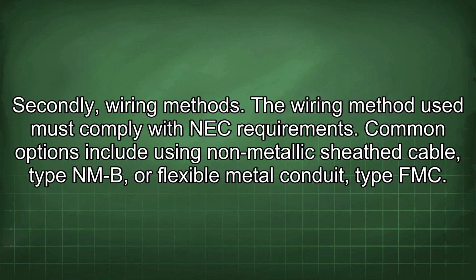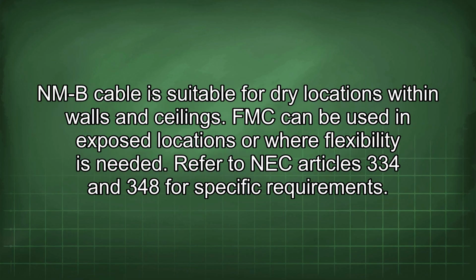Secondly, wiring methods. The wiring method used must comply with NEC requirements. Common options include using non-metallic sheath cable type NM-B or flexible metal conduit type FMC. NM-B cable is suitable for dry locations within walls and ceilings. FMC can be used in exposed locations or where flexibility is needed. Refer to NEC Articles 334 and 348 for specific requirements.